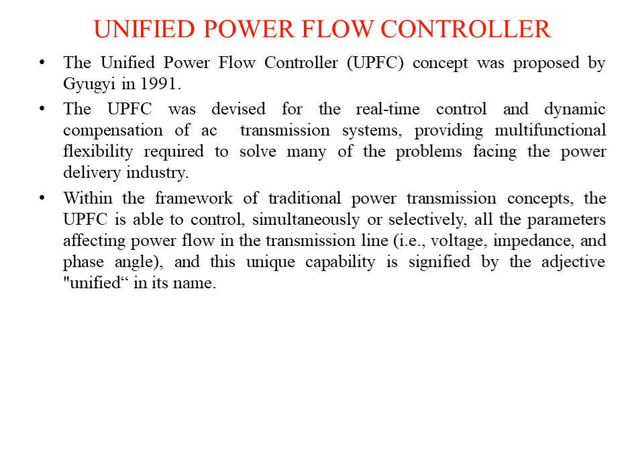Within the framework of traditional power transmission concepts, the UPFC is able to control simultaneously or selectively all parameters affecting power flow and transmission — that is voltage, impedance, and phase angle. This unique capability is signified by the adjective 'unified' in its name, meaning it combinedly controls voltage, impedance, and phase angle, thereby controlling reactive power, improving voltage stability limit and power factor, and eliminating or compensating harmonics present in the system.